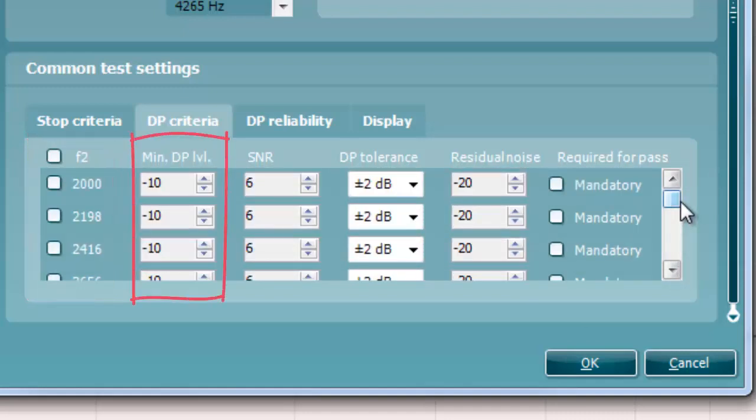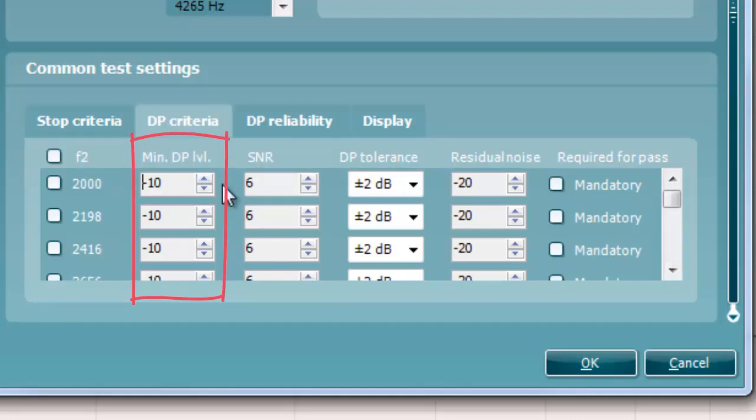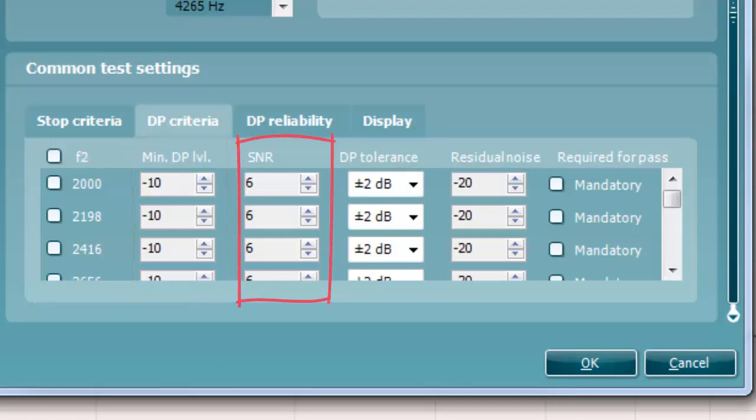DP level is the minimum level in dB sound pressure level that an OAE must be measured at for it to meet the stop criteria. SNR is the minimum signal-to-noise ratio that must be reached to meet the stop criteria. The signal-to-noise ratio in dB is the difference between the DP OAE level and the residual noise.